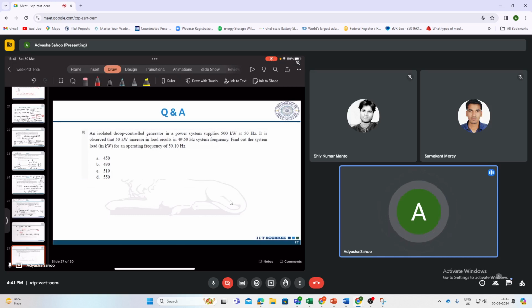So here isolated droop control is there. So it is telling that the generator supplies, let's say initially F naught, that is 50 hertz, and it was P1, and P1 is your 500 kilowatt. So 50 kilowatt increase in load.